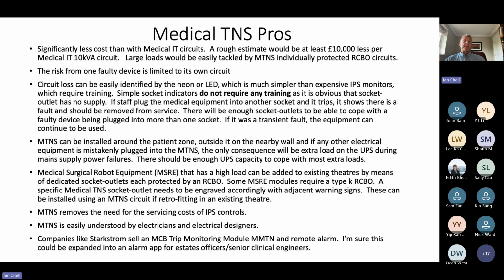The other advantage is that medical surgical robot equipment, which has a high load, can easily be added in the future to, say, a theatre that's already got medical TNS in. Quite simply, you just swap out two of the RCBOs for time delay. So again, an easy upgrade if you add a robot. As I said before, the Intuitive requires a type K RCBO, but they need to be specifically engraved accordingly with adjacent warning signs, okay?